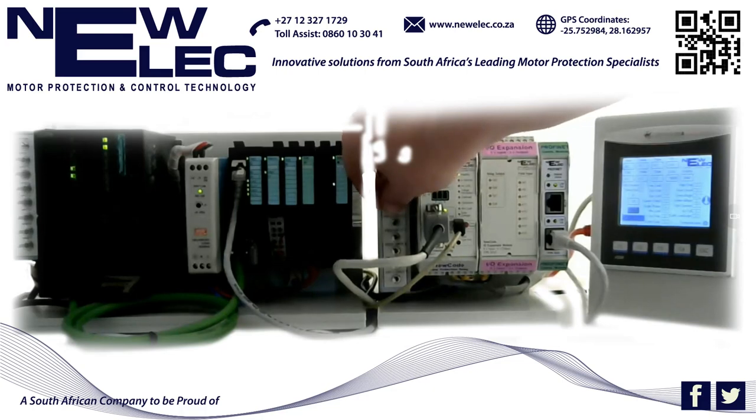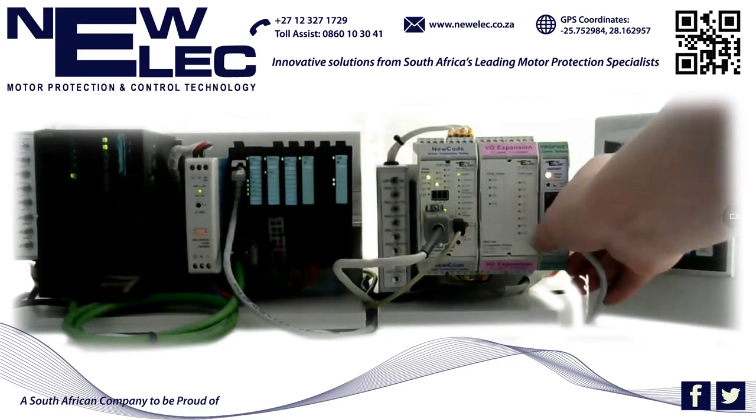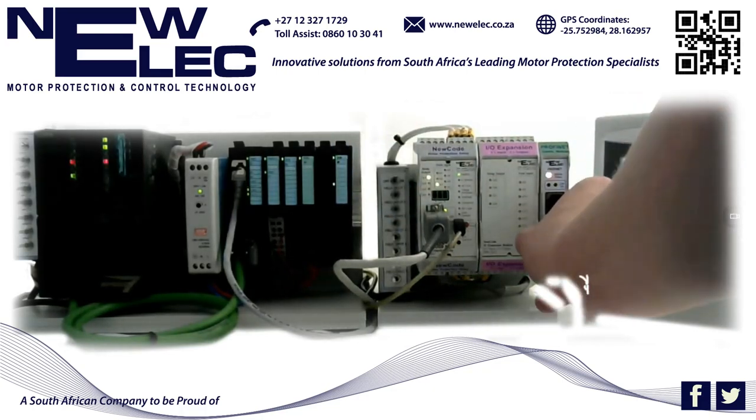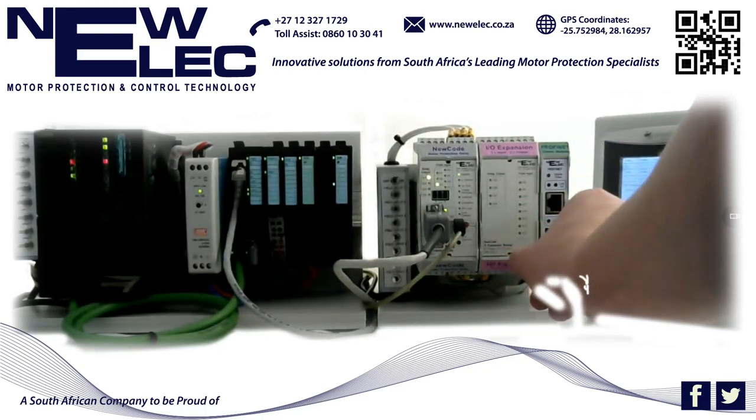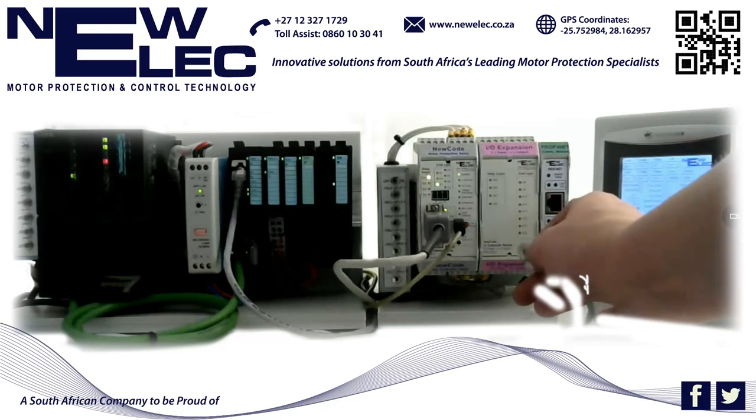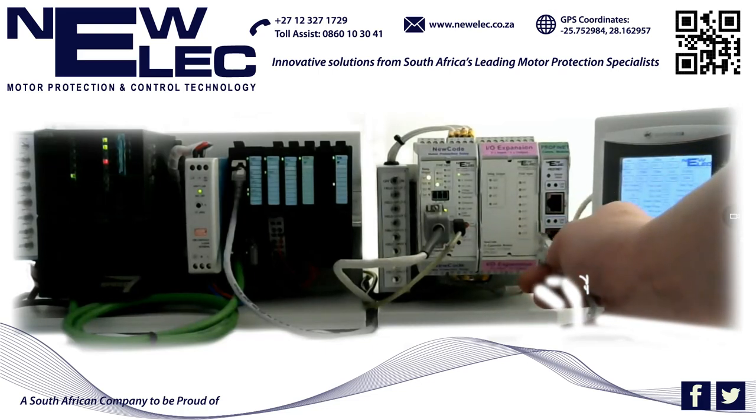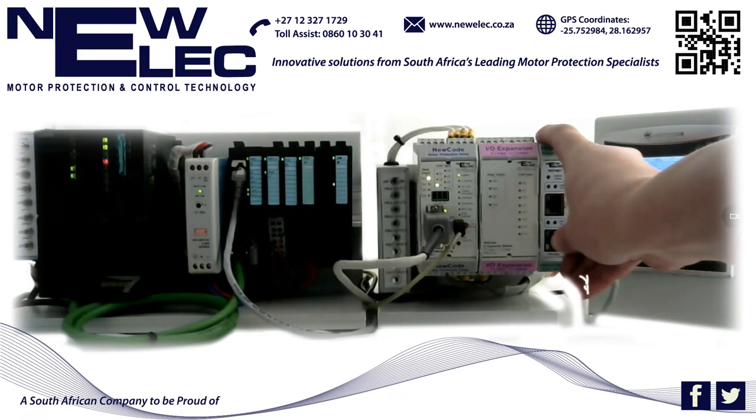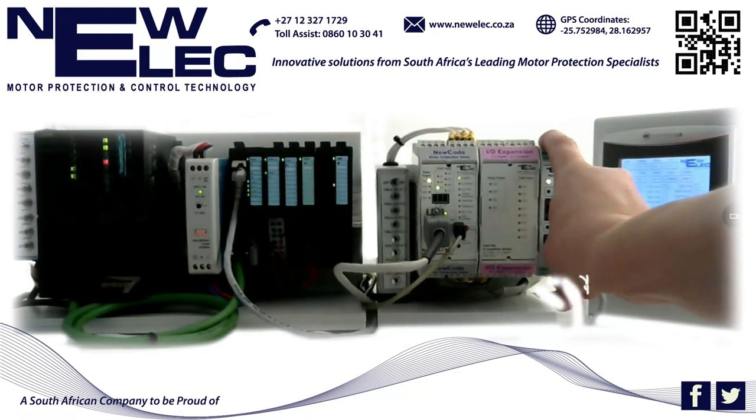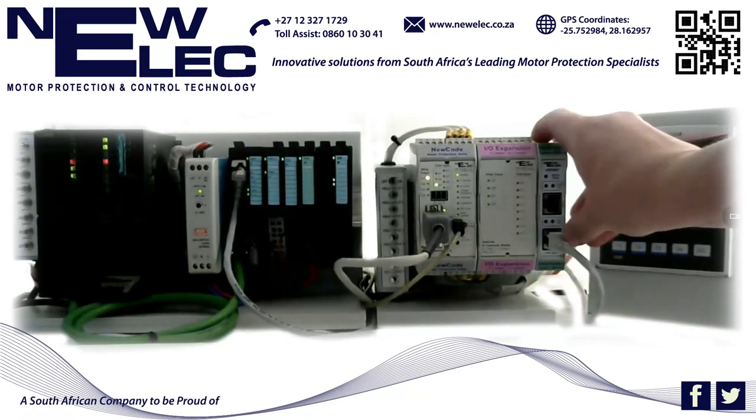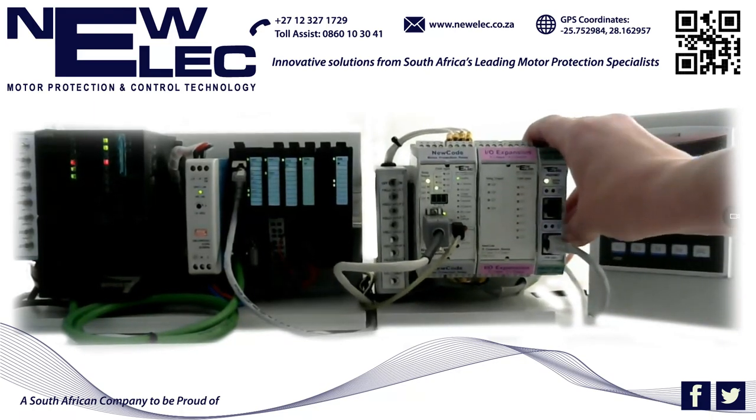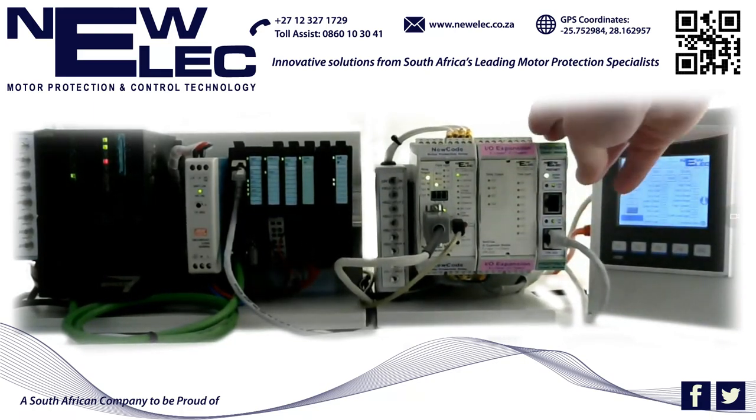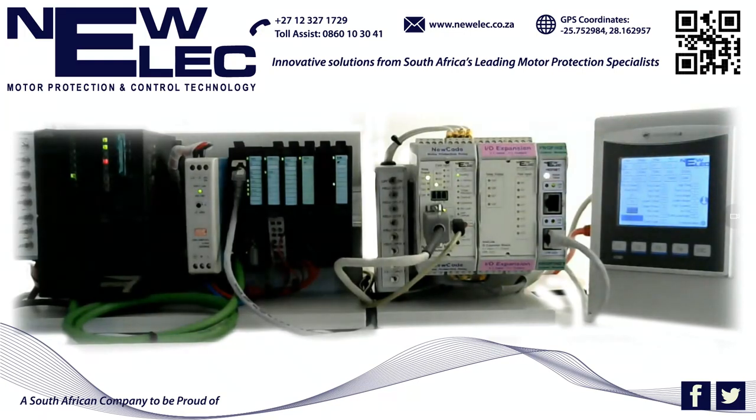When I pull out the PROFINET communication cable, you will see that the heartbeat immediately stops, indicating that the PROFINET module is not currently on the SCADA system anymore. This can be used to take action for when the PLC loses communication with the PROFINET module.